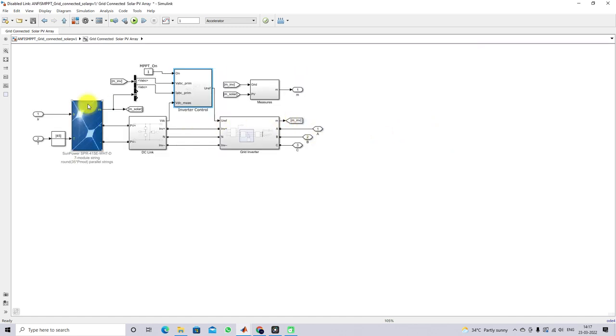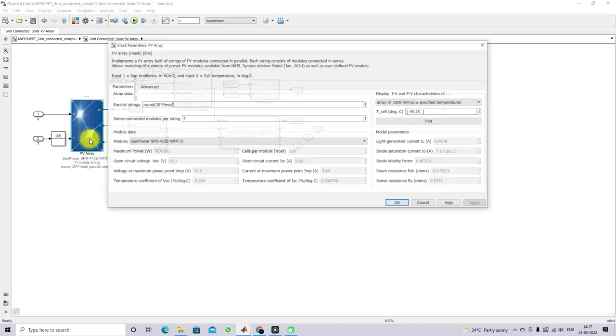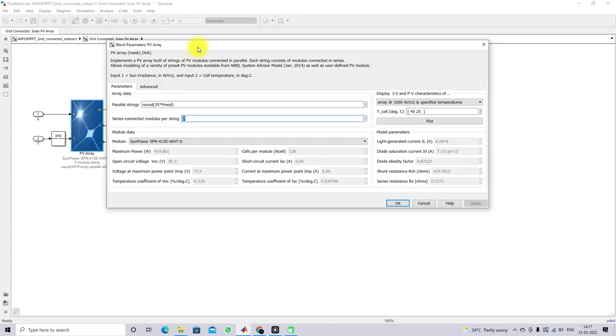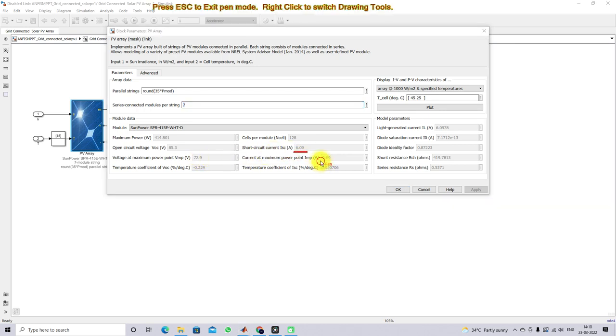Let's go and see this model - the grid-connected PV system. Here we have the PV panel details. The single panel power is 414 watts. The open circuit voltage is 85.3 volts, voltage at maximum power point is 72.9 volts, short circuit current is 6.09 amps, and current at maximum power point is 5.69 amps.